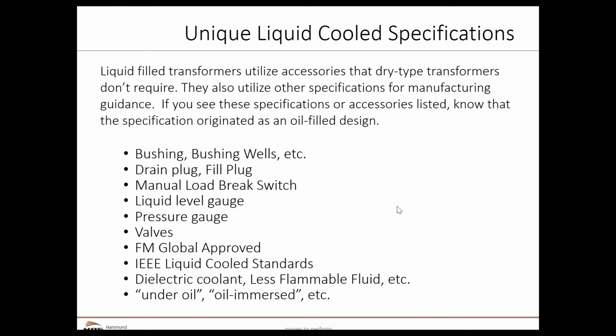Manual load break switches are, again, something that's more common within these transformers. There are certain things that I can do with a switch that's also surrounded by the oil that the transformer is using that I can't do as easily if it is what we call an air switch, a normal switch that operates in the air versus something that is submerged in oil. Obviously, things like liquid level gauges and pressure gauges all indicate that I'm using some type of a liquid.